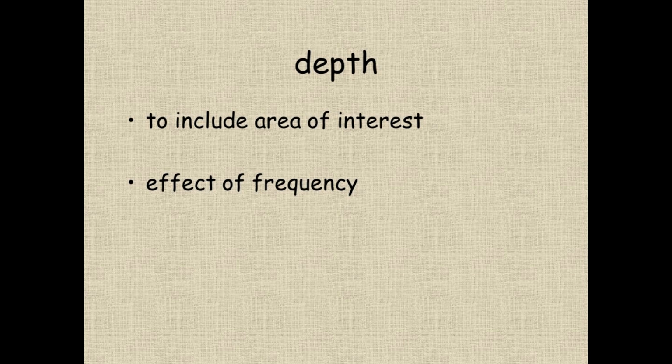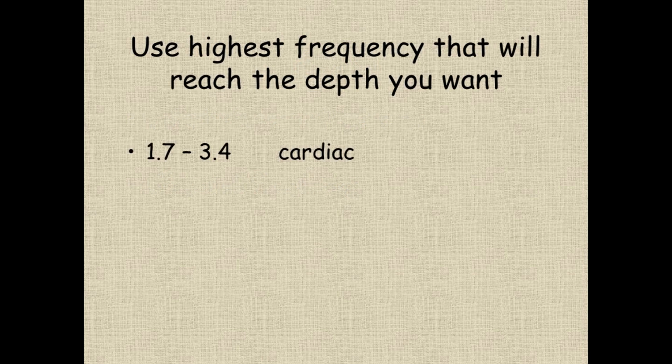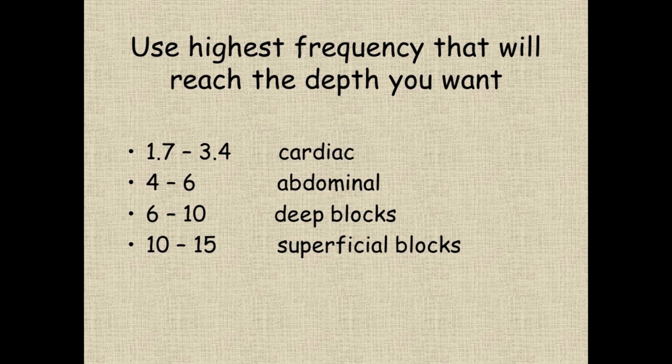The depth setting you select when setting up your ultrasound machine should include the area of anatomical interest and should consider the effect of frequency. The general principle is to use the highest frequency you possibly can that will still reach the depth that you want to interrogate. Generally, in medical ultrasound, these are the sort of frequencies in megahertz that are used for different applications.